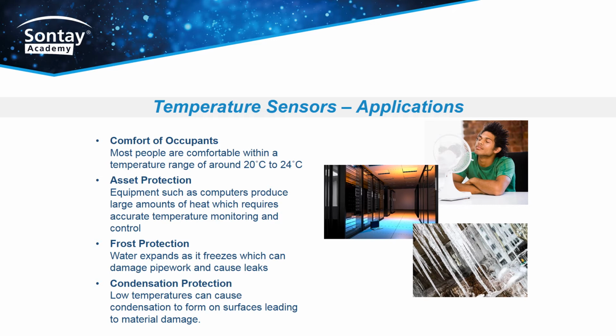The primary reason for sensing temperature is to provide comfortable conditions for building occupants. However, some applications, such as data centres, require accurate temperature monitoring to ensure the excess heat generated by IT equipment is removed from the space in an energy-efficient manner. Temperature sensing is also vital in providing frost protection to water systems susceptible to low temperatures. Water expands as it freezes, which exerts huge pressure on pipework systems and can cause weak points to rupture, causing a leak when the system thaws.